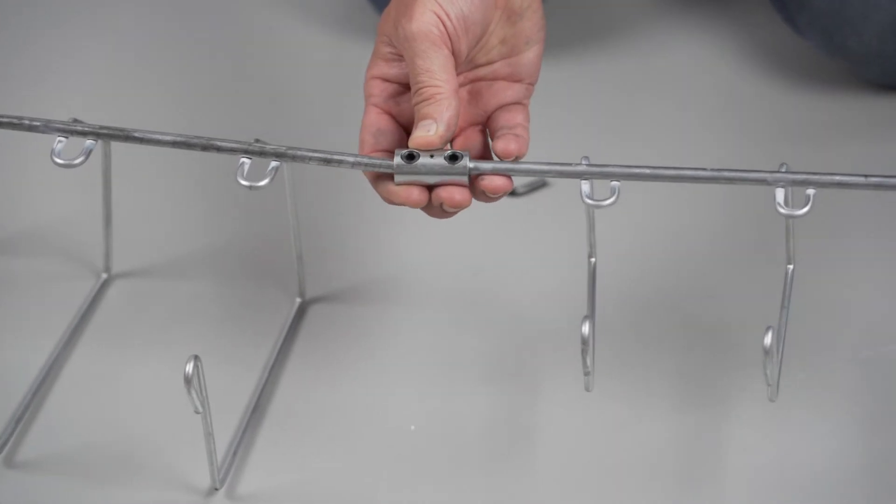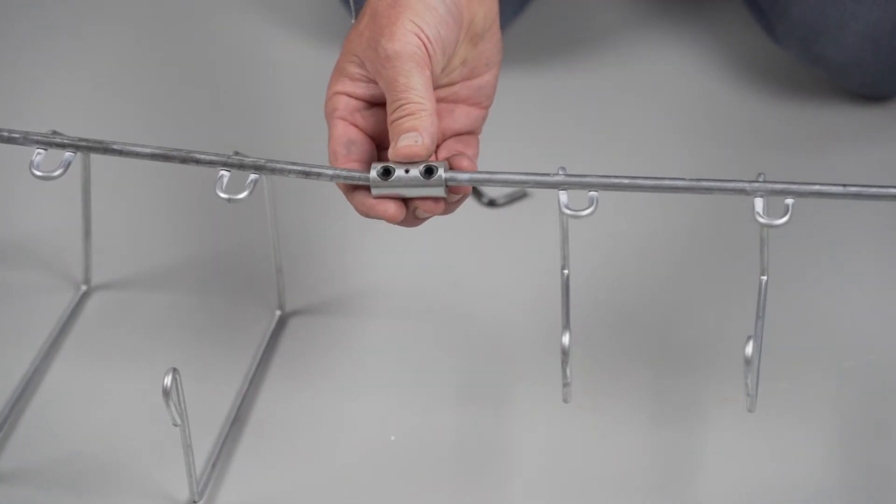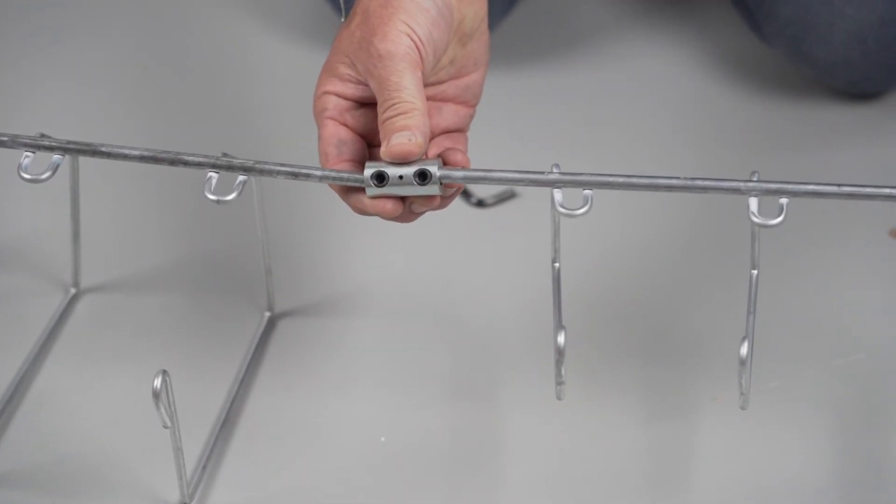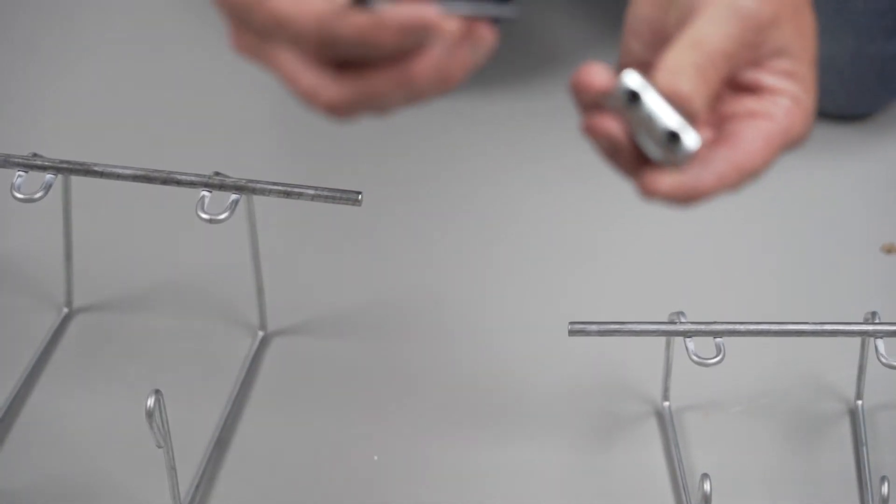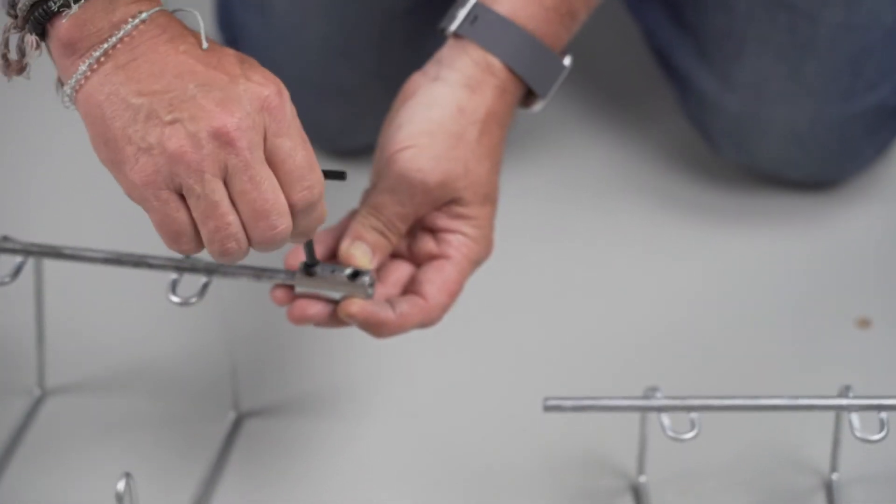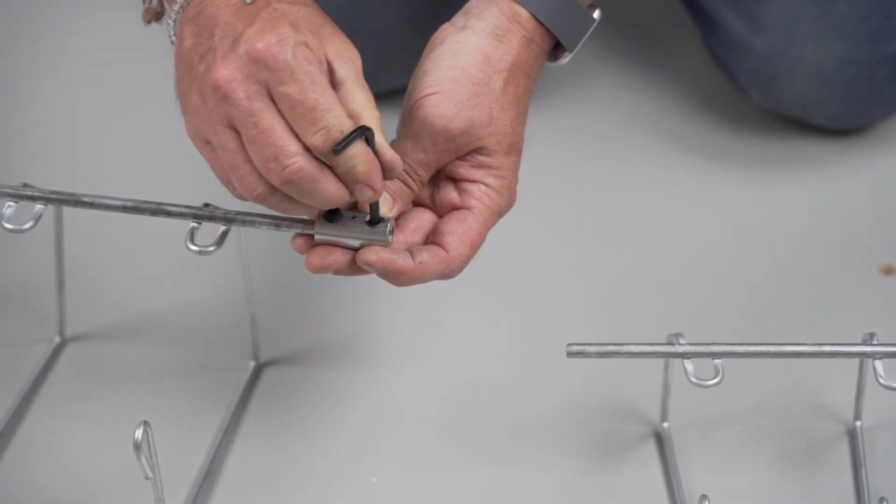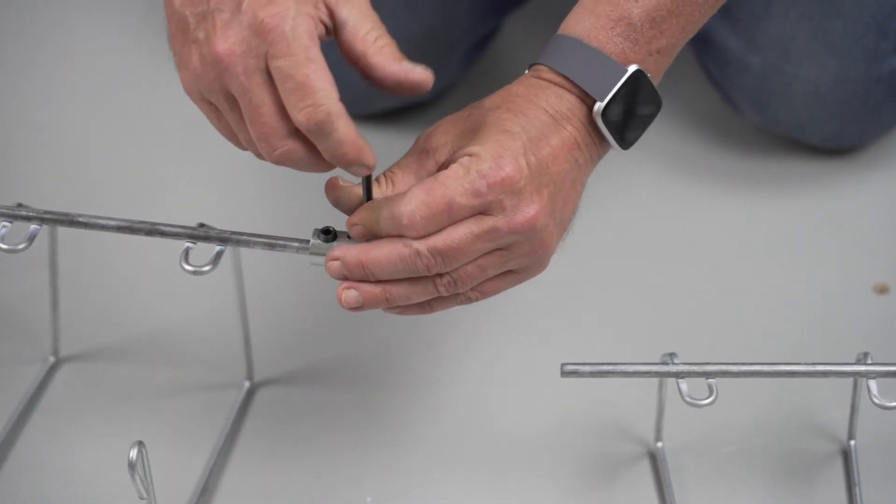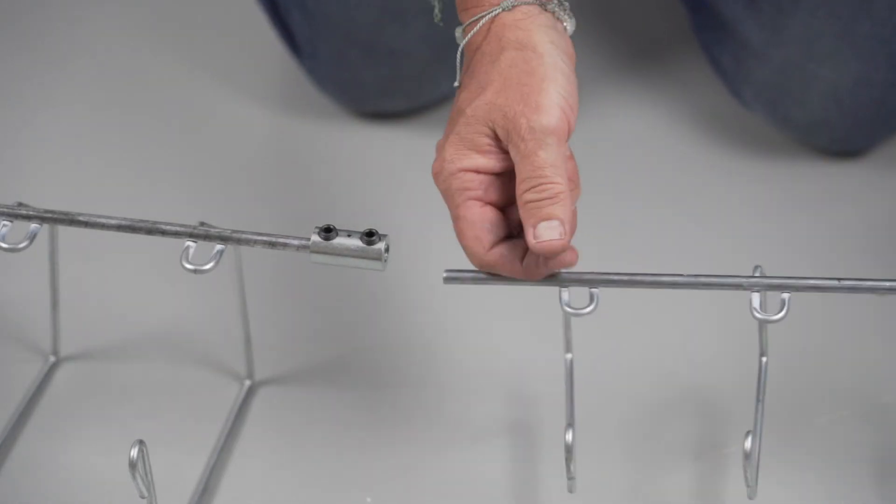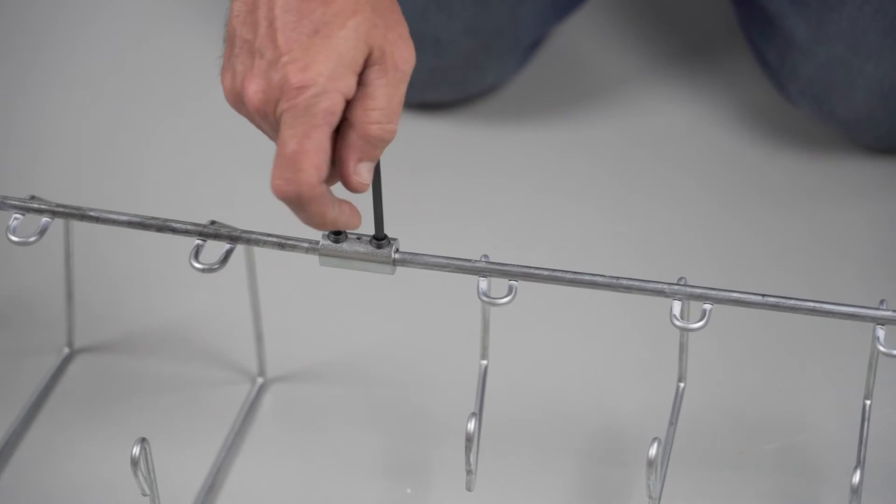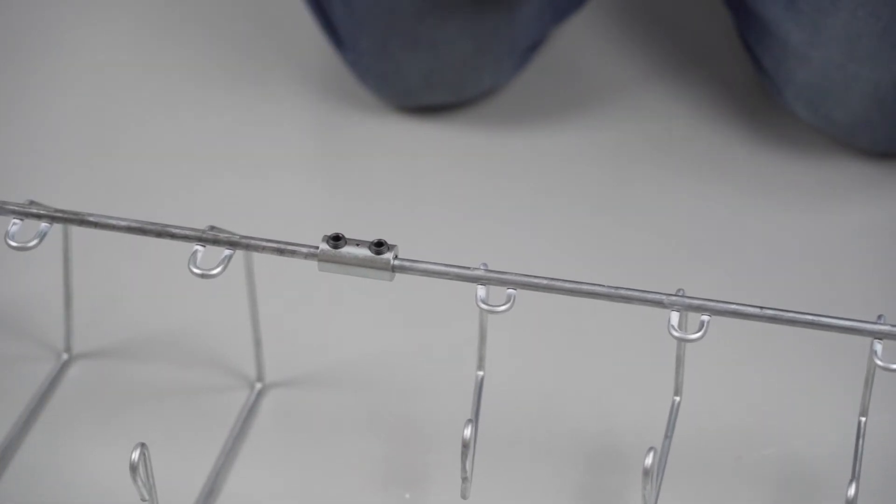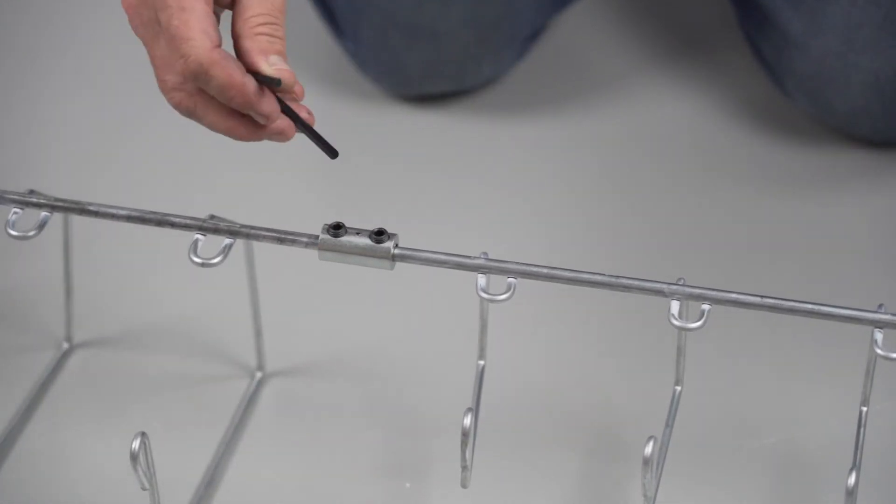We'll put the two spines together just like so. Okay, that makes a bonded connection as well as a mechanical and it's set up with some Allen set screws to tighten down. So one end will go on to the spine. Put that down. Put our other section together. Insert that into the barrel bolt. And then tighten up with an Allen wrench. And again it's a mechanical as well as our electrical bond.